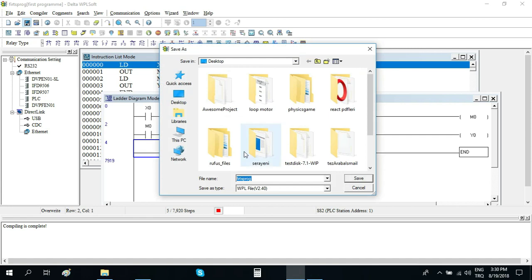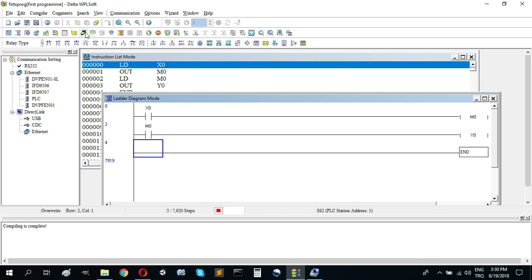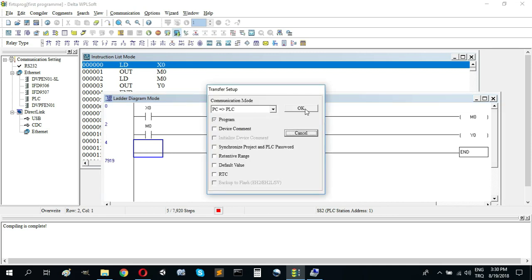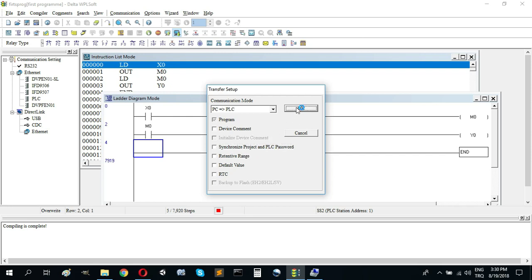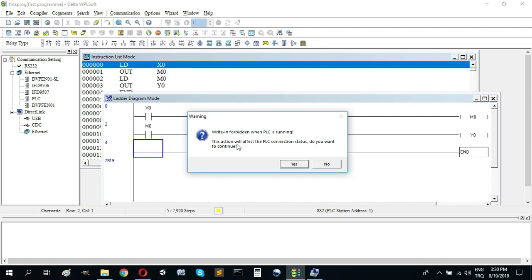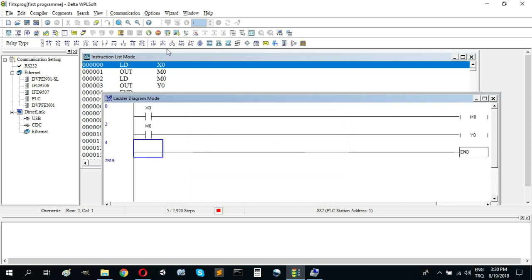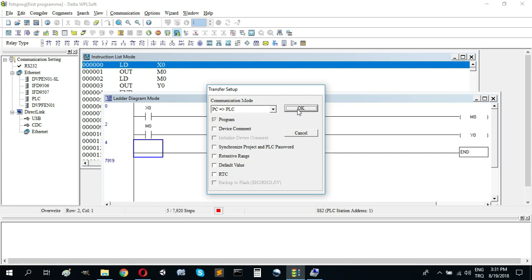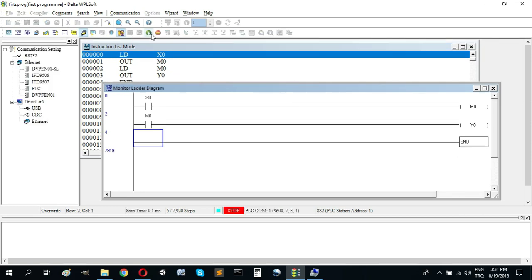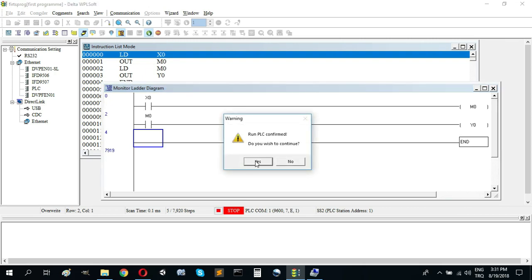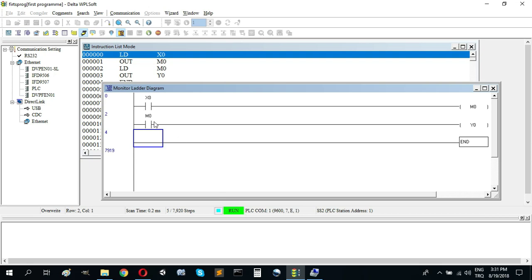Now I can compile. We can click online mode, but before that we should send the program to the PLC. A warning appears because the PLC is running — writing is forbidden while running. We should stop the PLC to write the program, then click OK. Now we have the program in our PLC.